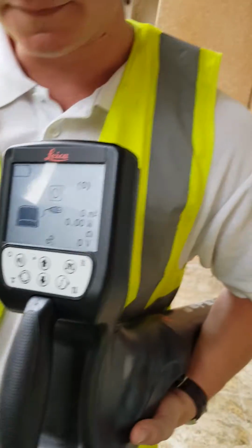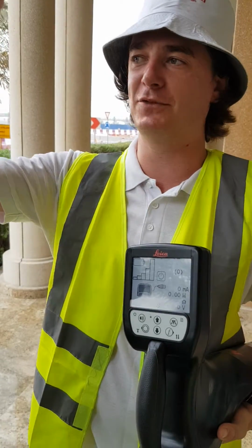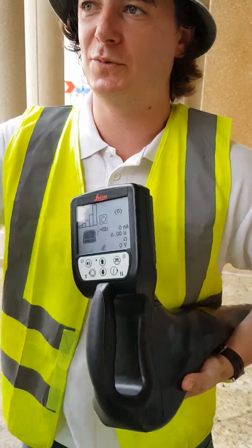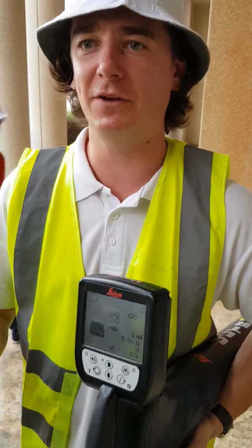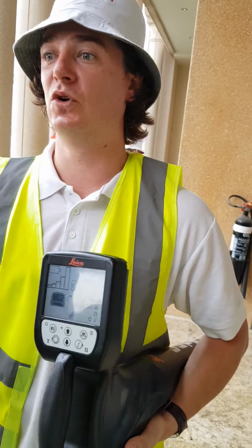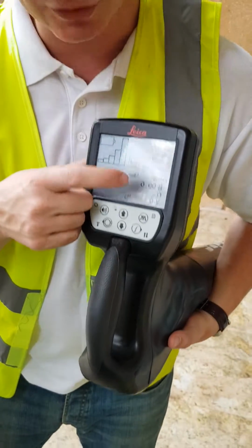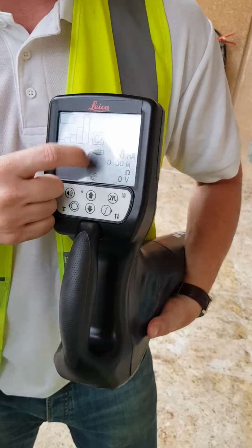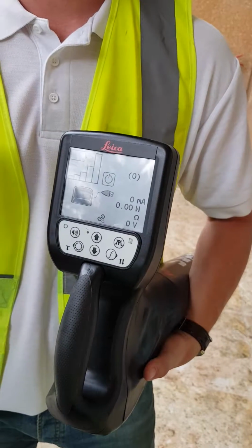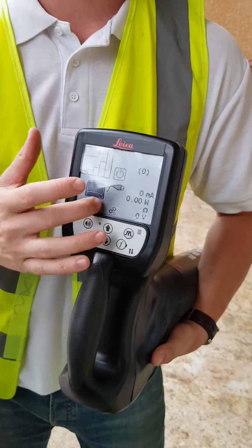Yesterday the guys were tracing the street lights and the signal went from 600, which it had been for everybody, down to 30. And you guys said there was a problem, something's gone wrong, what's going on with the locator. I walked back to the transmitter and I realised the transmitter has either been moved or the ground's dried out and the earth wasn't good. On here there is a symbol that would turn up, and we'll see this later when we connect them. There's a symbol with the target to show you that you've got a good earth. If you've not got this target, it will be a warning triangle saying you have no earth. That will be a problem.